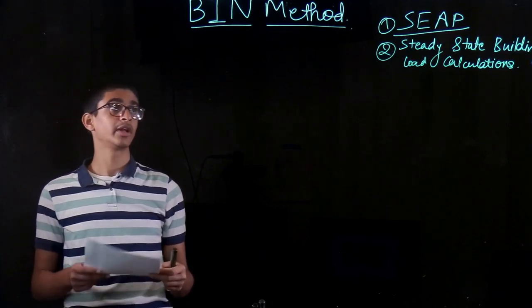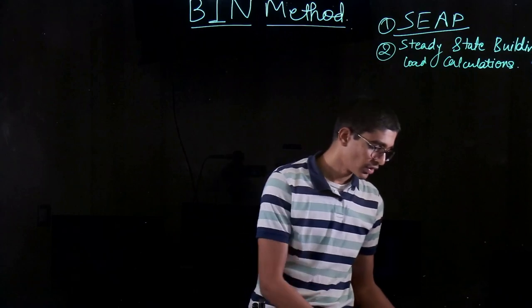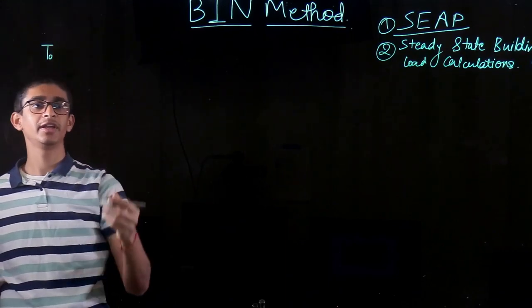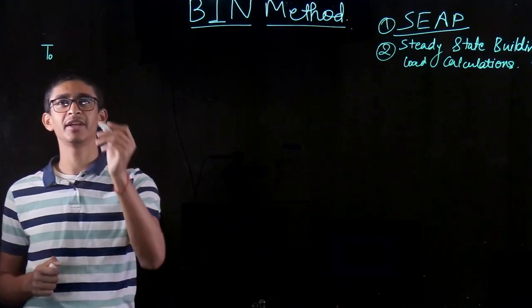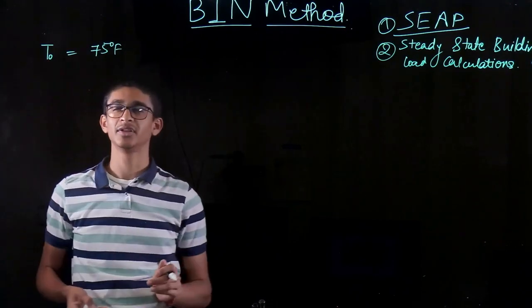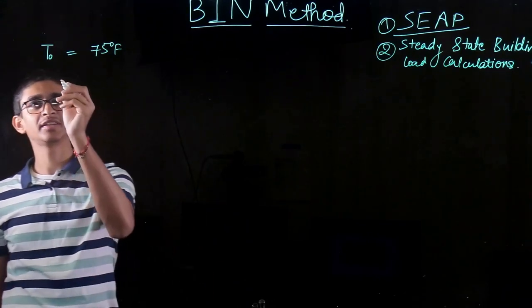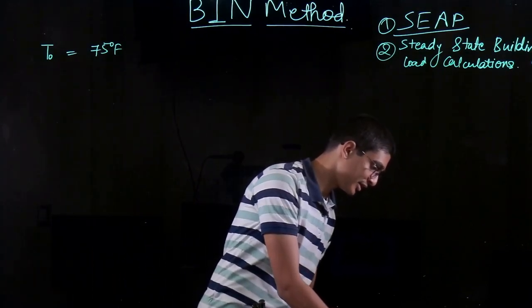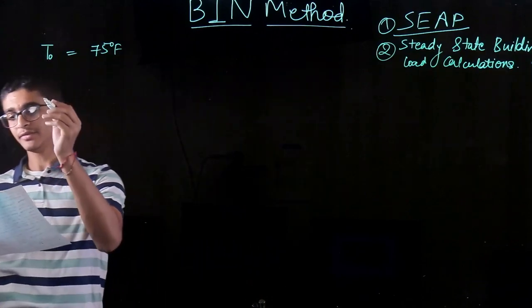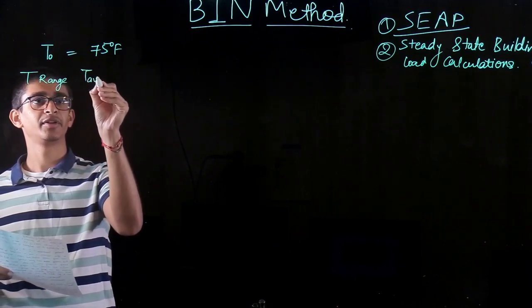This allows us to have more accurate energy load calculations, and as I explain the method it will become clearer. Basically, in the BIN method, we have an outside temperature that varies based on months or time periods. So instead of having one constant average temperature of, say, 75°F for the whole year, what we do is split the outside temperature into various bins. Let me use a proper example.